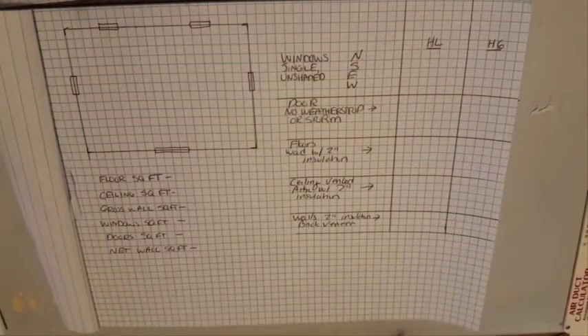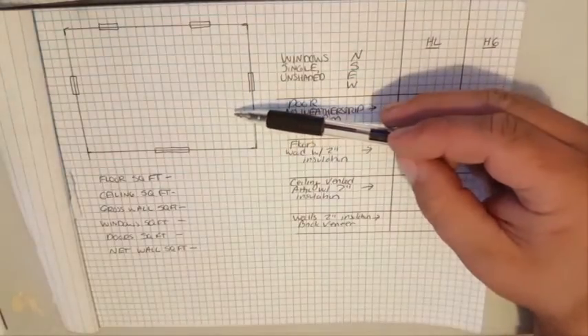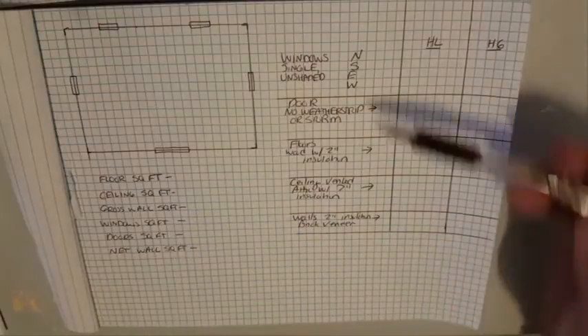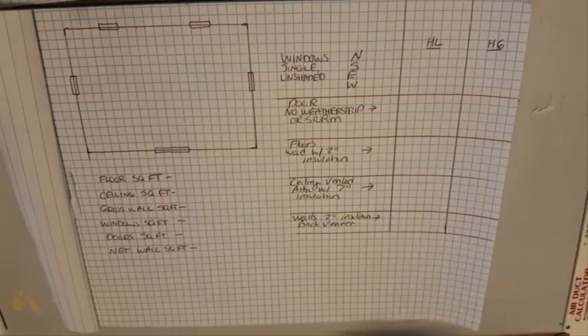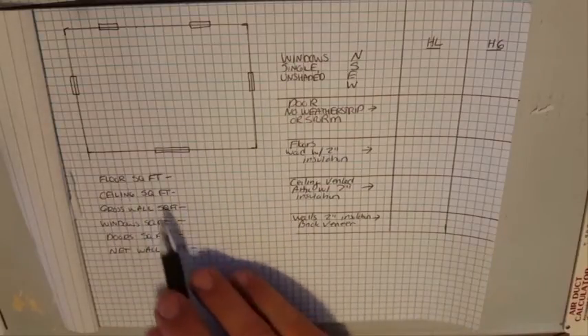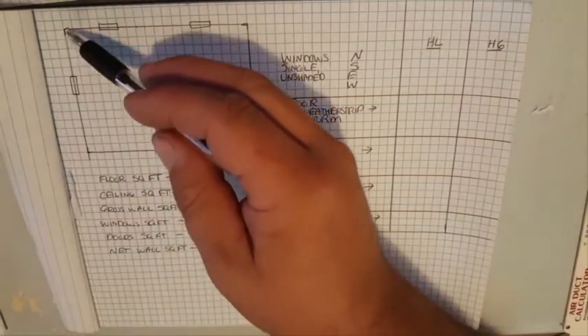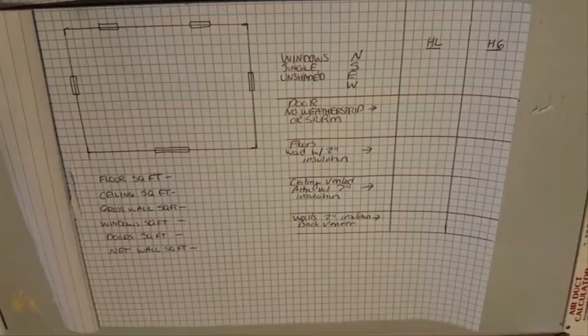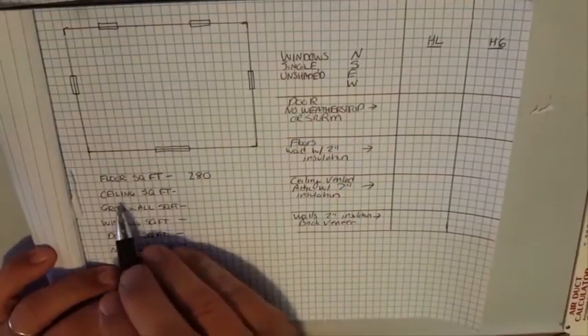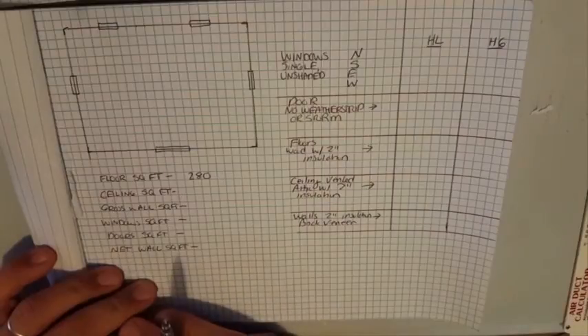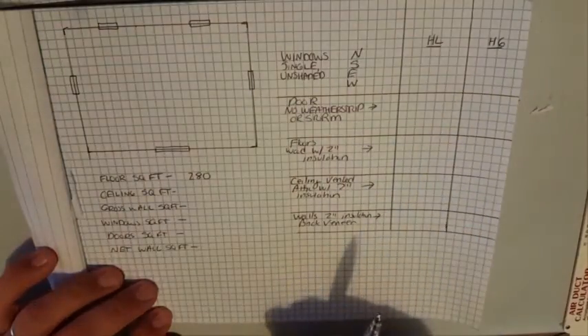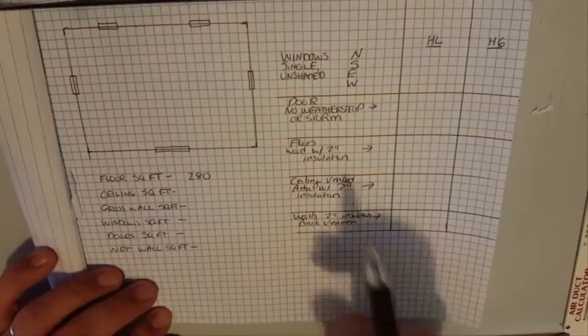Guys, we're moving on to page two and I kind of tidied it up a little bit. Here we have our building drawn, we have a few square footages we're going to get, and then we have some heat loss and heat gain multipliers to figure out. So let's look at the building here. The first thing is the floor square foot - we're 14 foot by 20 foot, so that puts us at 280 square feet. I'm going to go ahead and write that in. Our ceiling square foot and flooring square foot will be the same because we're going to have a flat ceiling. We'll do a different video to figure out how we get the area of a vaulted ceiling.